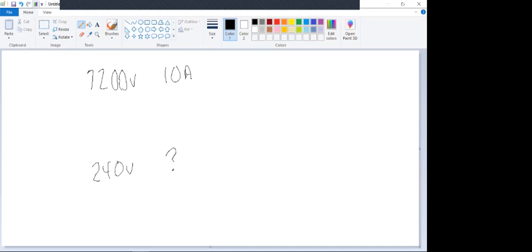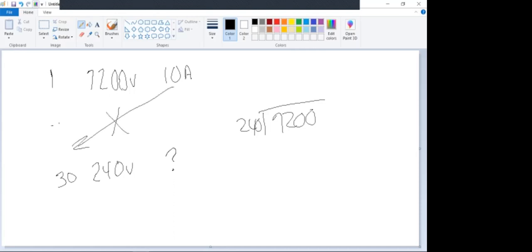The student figured the ratio out here. So how'd you figure the ratio? 7,200 divided by 240, which is 30. So that's a 30 to 1 ratio. Then you multiply 10 times 30, which is 300, and that gives you 300 amps. Thank you very much.